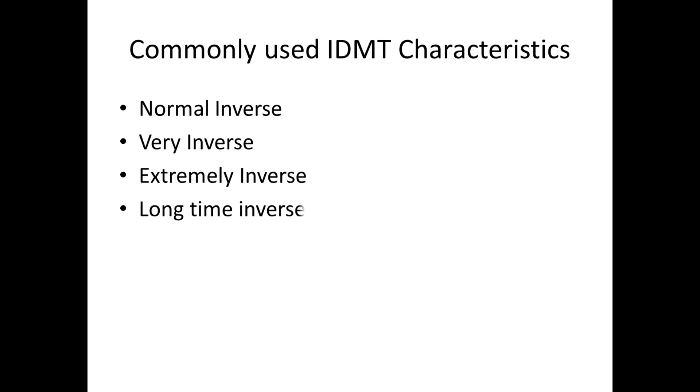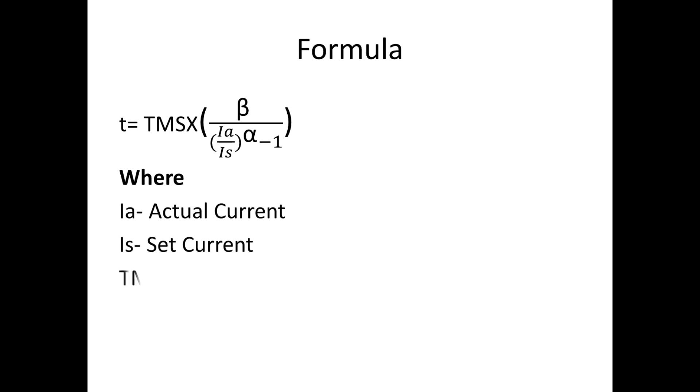For all these curves generally we have one formula. T is equal to TMS times beta divided by (Ia/Is) to the power alpha minus 1. Where Ia is actual current, Is is set current, TMS is time multiplier setting.